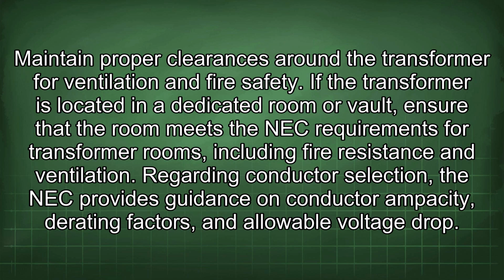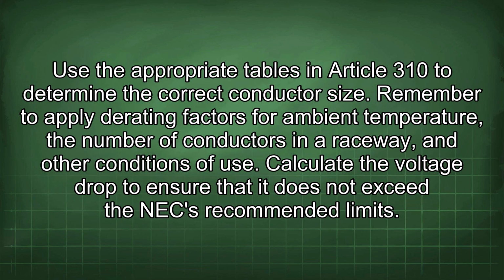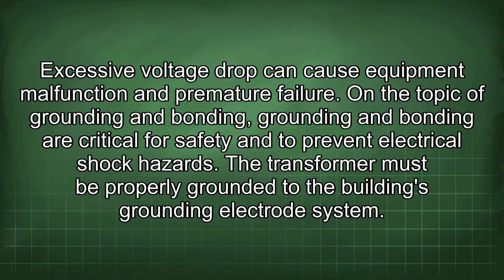Regarding conductor selection, the NEC provides guidance on conductor ampacity, derating factors, and allowable voltage drop. Use the appropriate tables in Article 310 to determine the correct conductor size. Remember to apply derating factors for ambient temperature, the number of conductors in a raceway, and other conditions of use. Calculate the voltage drop to ensure that it does not exceed the NEC recommended limits. Excessive voltage drop can cause equipment malfunction and premature failure.